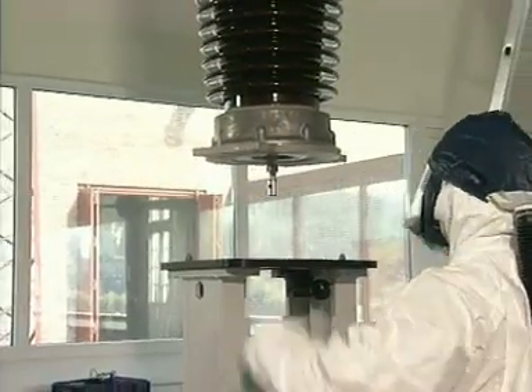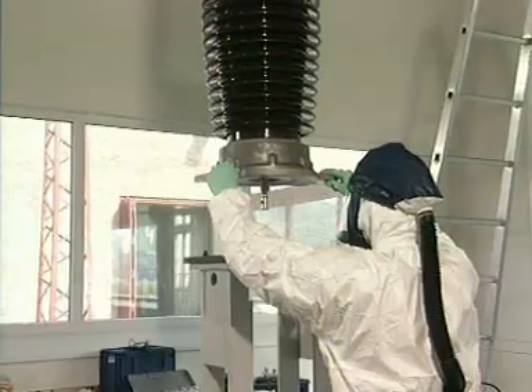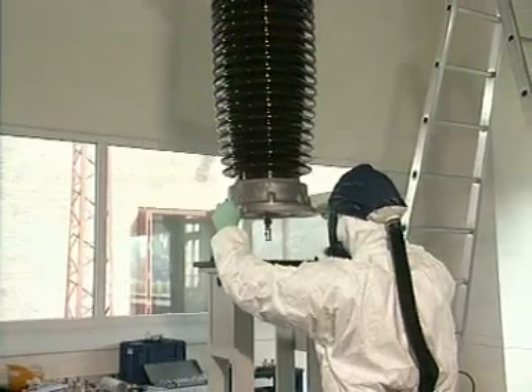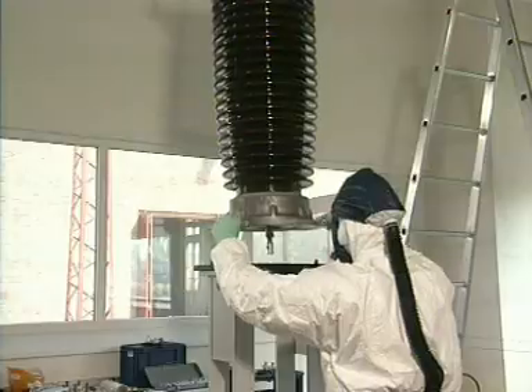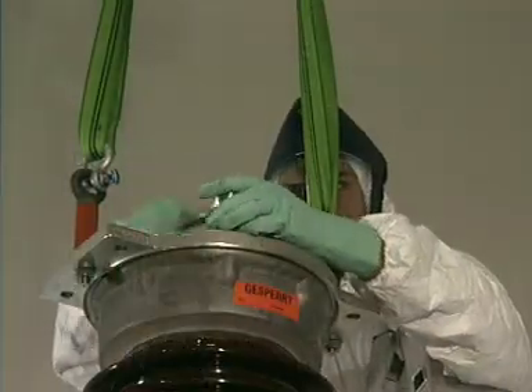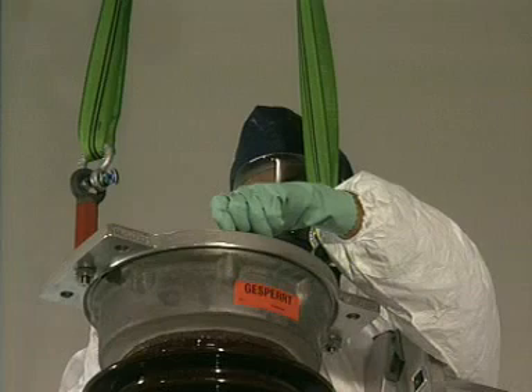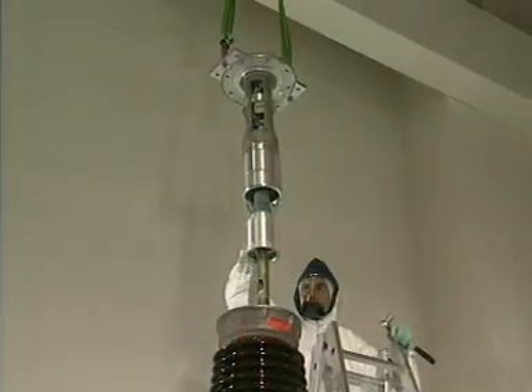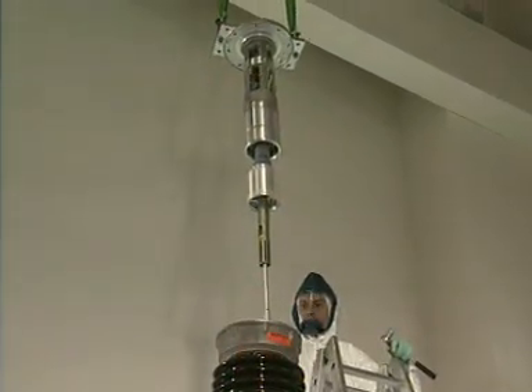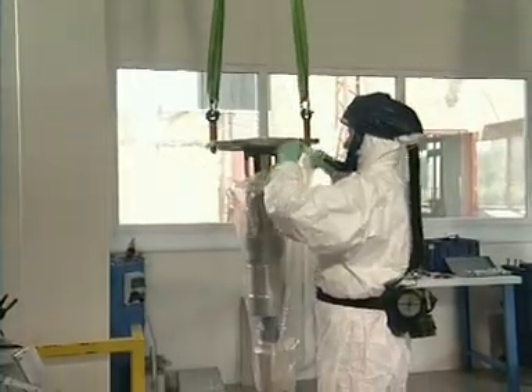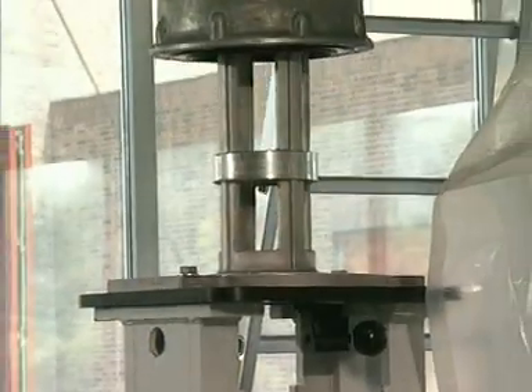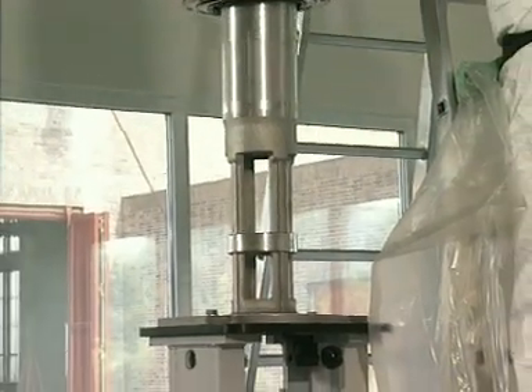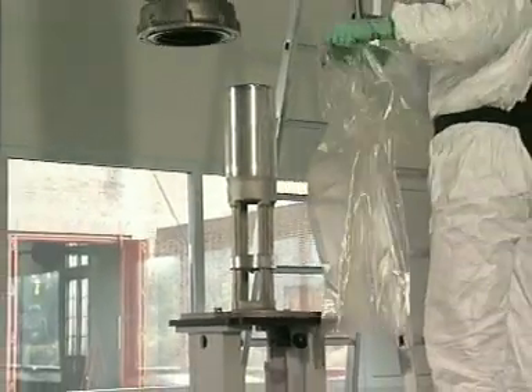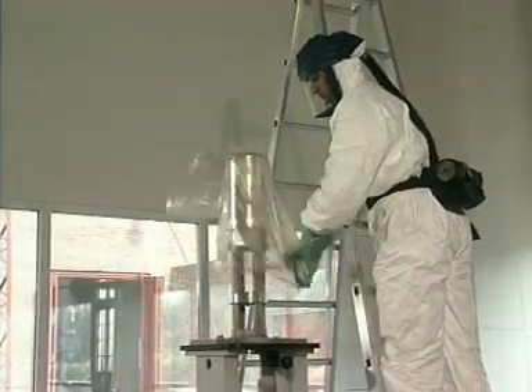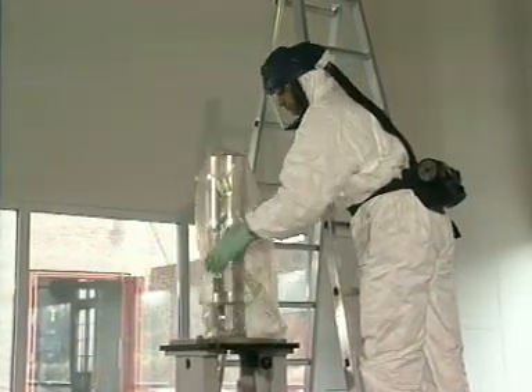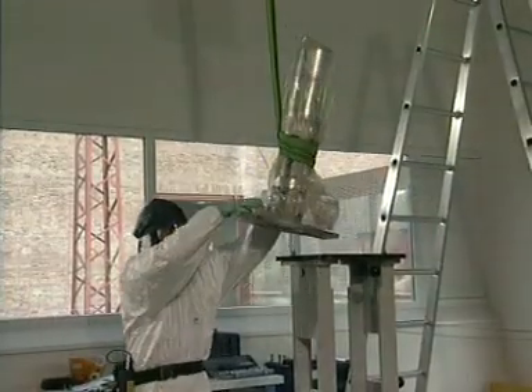Place the chamber on a mounting device and secure it. Loosen the screws on the upper flange. Pull out the double motion unit and wrap it in dust-tight packaging. Loosen the screws on the lower flange, lift off the chamber porcelain and place it on a suitable surface. Wrap the contact carrier in a dust-tight packaging and remove it from the fixture.